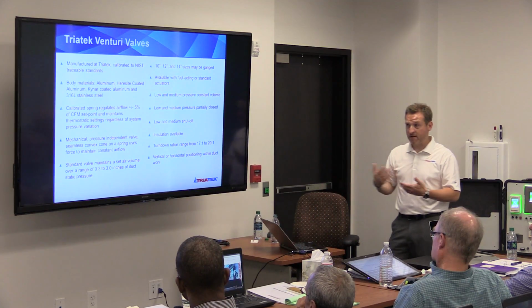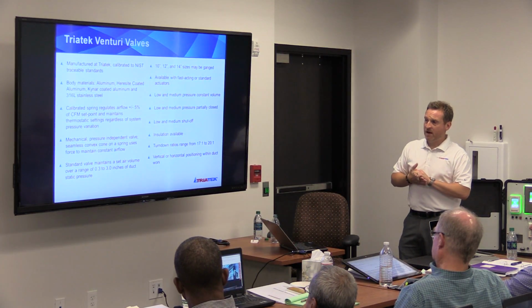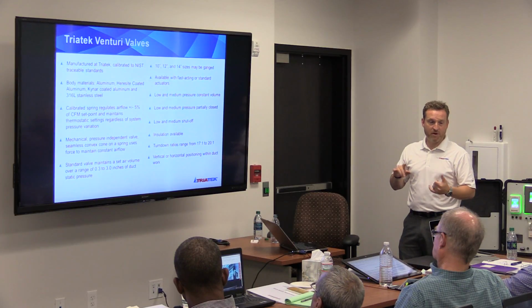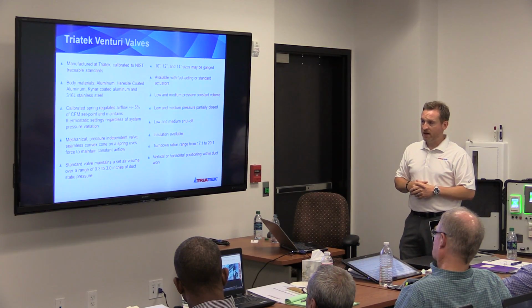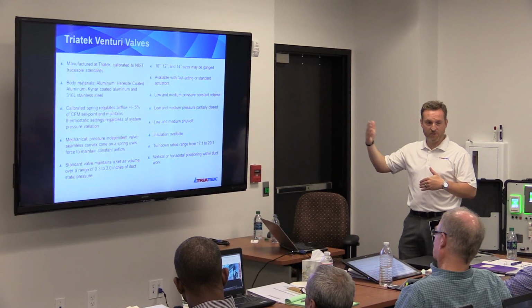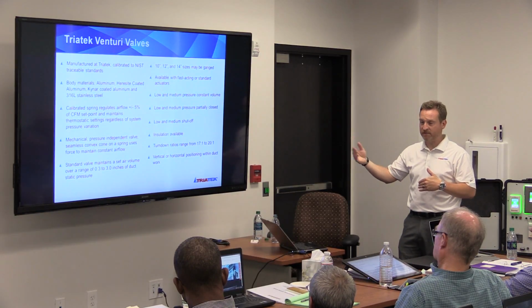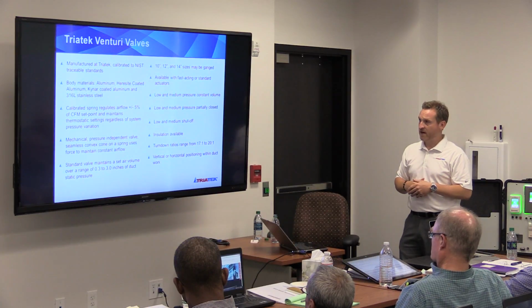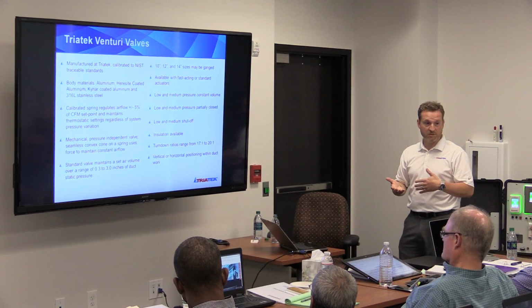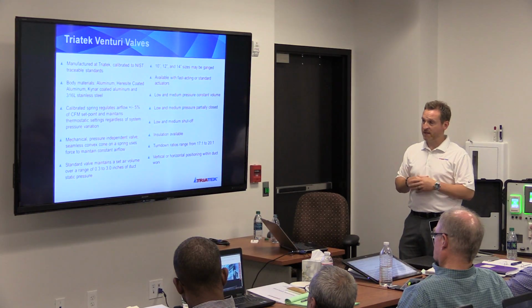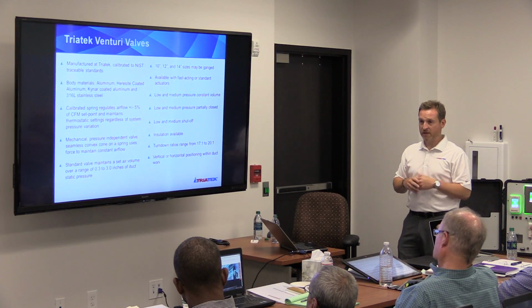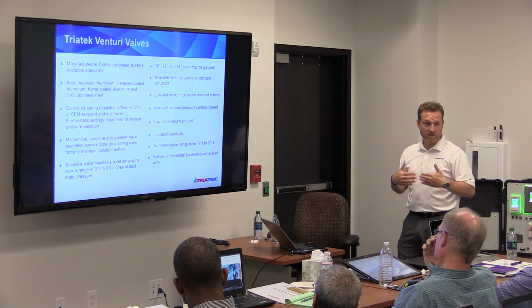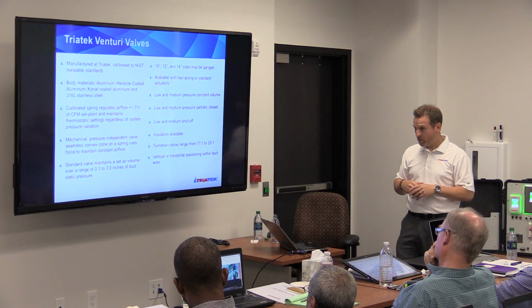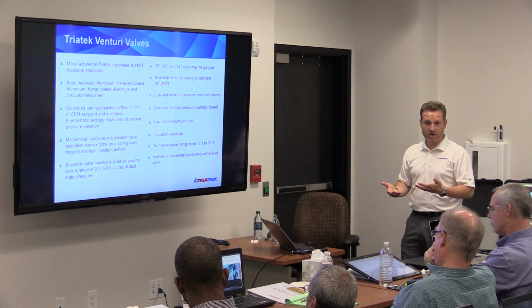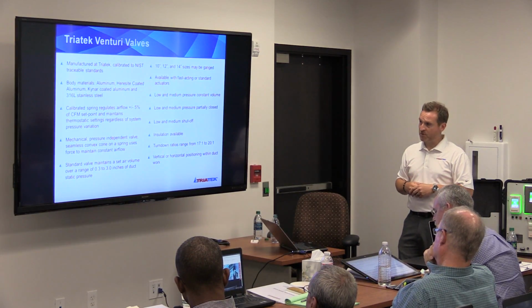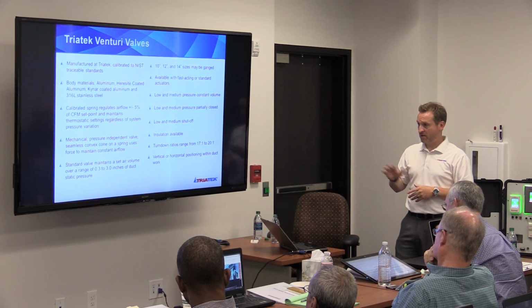As I said, our mechanical pressure independent valve comes in two pressures, both low and medium pressure. The lower pressure valve will allow you to run your fan statics at lower pressure for energy savings. We also offer the valves with full shut-off or partially closed. Once again, that drives some of that energy savings, where you can shut those valves down for lower air change. We also offer the valve with insulation as well. So for your supply makeup valves where you'd have condensation, insulation would be good for that.